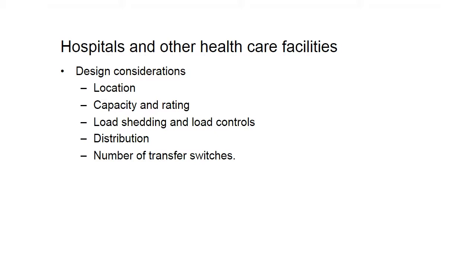Looking at the capacity and the rating, the systems need to have adequate capacity to serve all of the required essential electrical loads. And you want that to be sized so that they can all be operated simultaneously. If you have optional loads, you'll want to take that into consideration as well and look at how that might or may not impact the size of your system and your generator requirements. Other considerations is possibly use for peak shaving, although there are specific requirements from a code perspective and constraints on that.